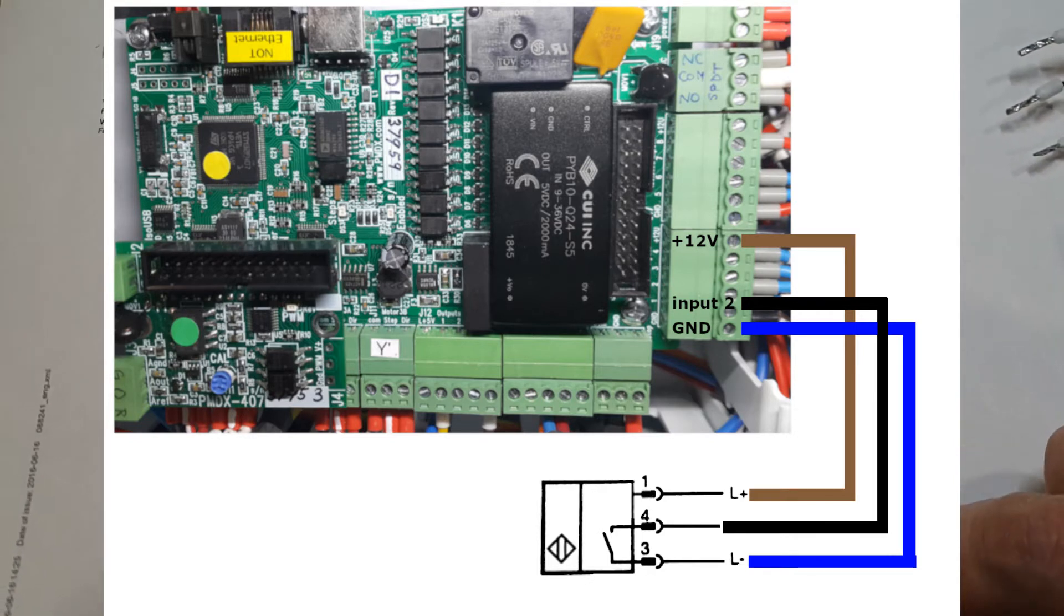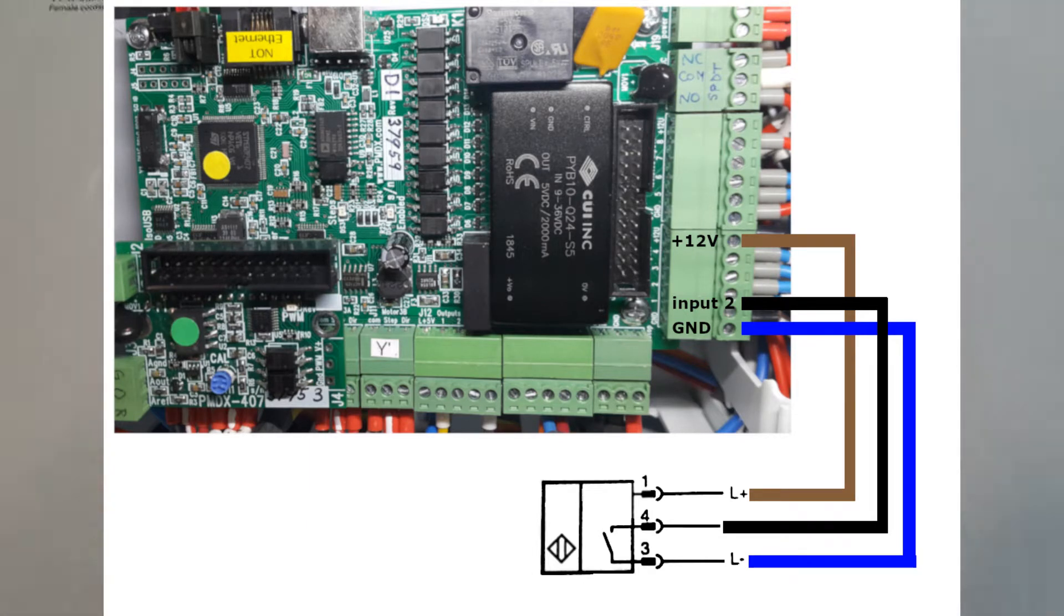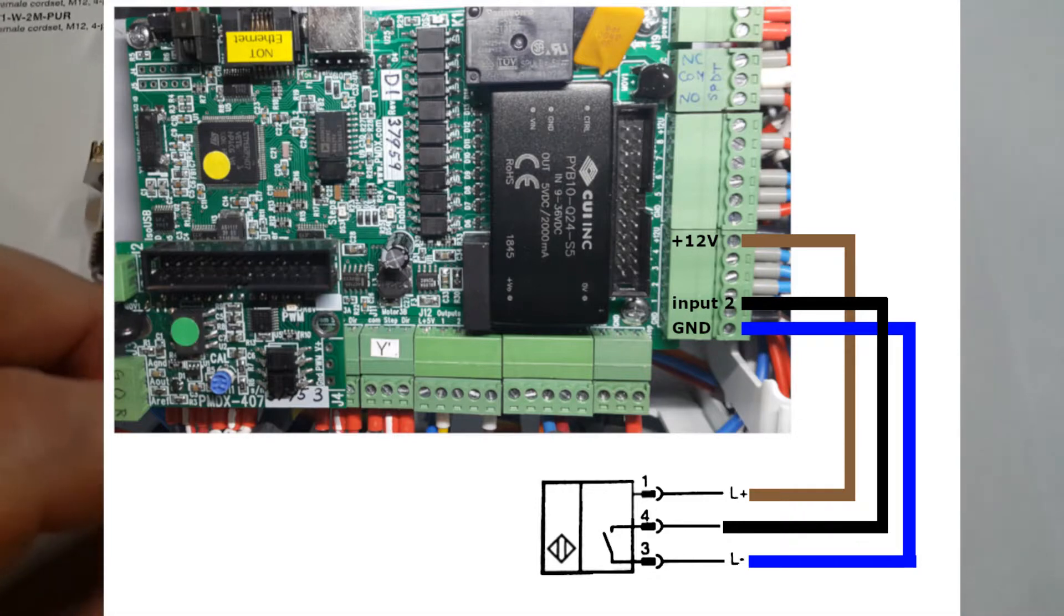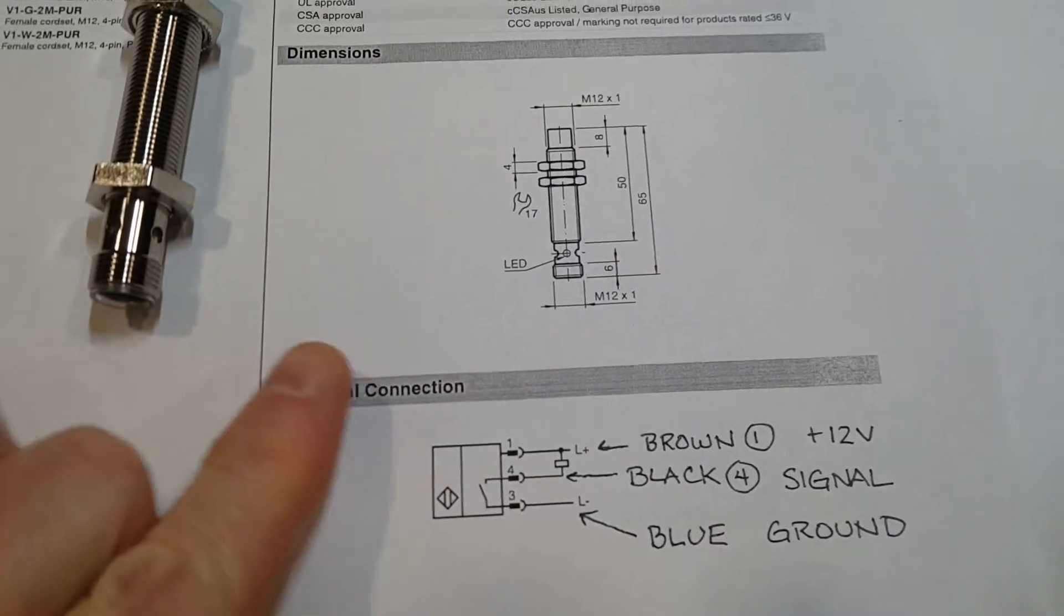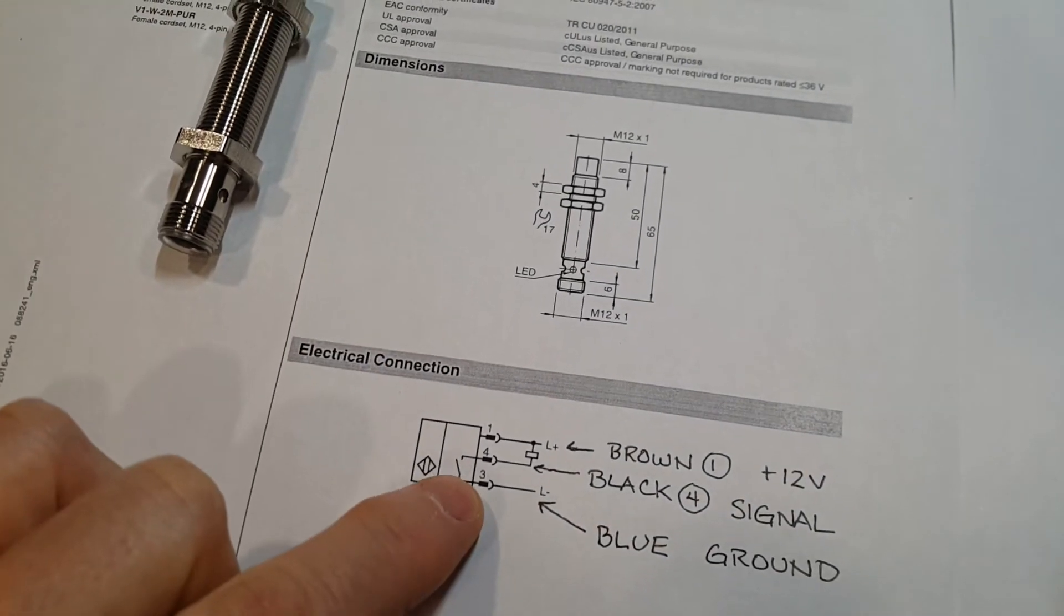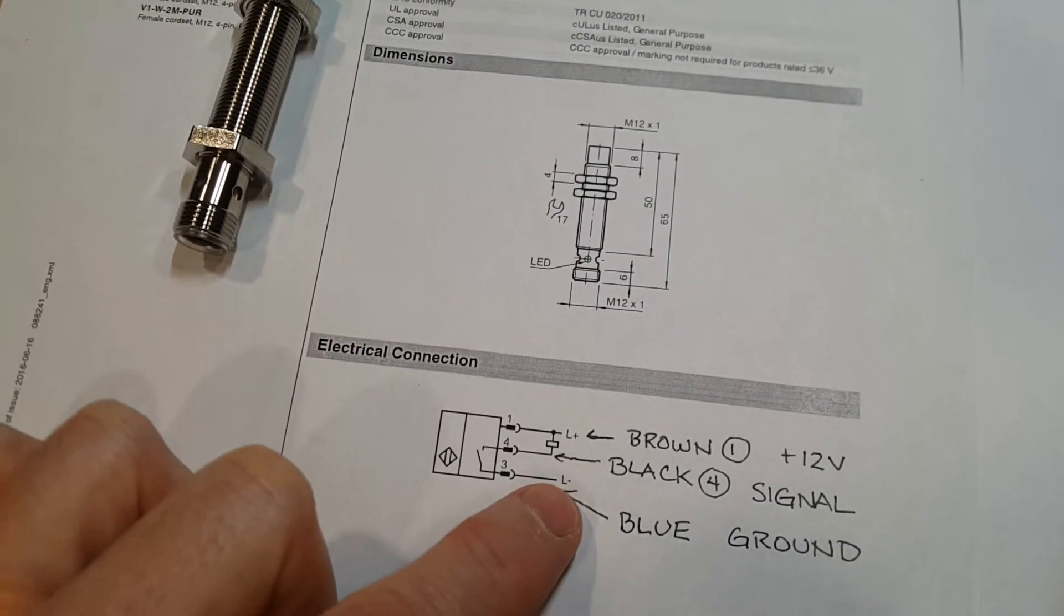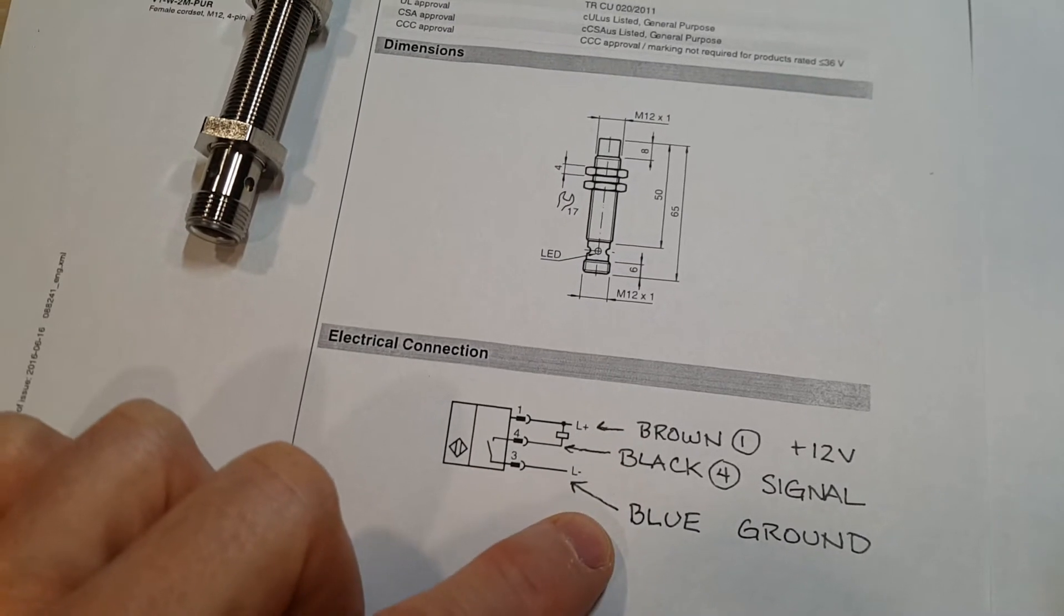We're also bringing ground from those input blocks, and then the signal wire goes back to the input block on the PMDX 424. Essentially, when a piece of metal comes to the end of the proximity sensor, this switch is closed and it pulls that input pin to ground, and that's the signal.